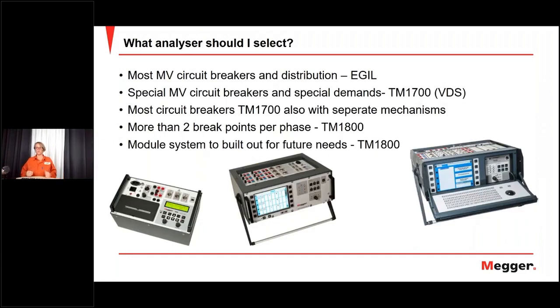So to work with outdoor breakers, I would really recommend the Team 1700 or Team 1800. And depending on how many breaks per phase, you will need to use Team 1800. If it has 3-4 breaks per phase, then it's a Team 1800. Also, if you want a modular system to build out with more channels in the future, also Team 1800 is a more flexible choice.